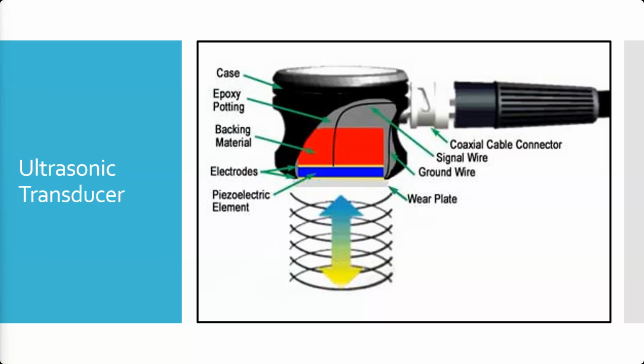What that means, though, is that the signal is being generated and received if it's a transmit-receive motion, or if you've got two of these, one's a transmitter, the other one's a receiver. There's going to be a slight difference from the actual crystal to our part, right? Our part, or the material we're testing, is going to be on the other side of that wear plate. So there is a slight offset that we have to take into account. One of the items you have to set as part of your calibration setup process is the offset to take into account that very small difference between where the crystal is and where the front face of your part begins.